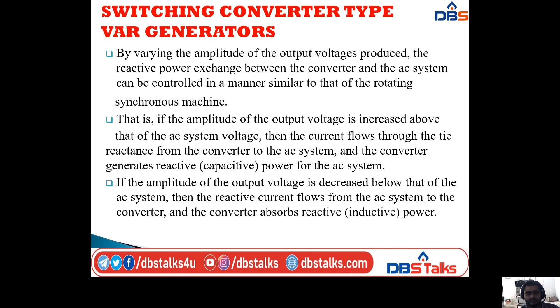If the amplitude of the output voltage is decreased below the AC system voltage, reactive current flows from the AC system to the converter, and the converter absorbs reactive power. If the output voltage amplitude equals the AC system voltage, the reactive power exchange is zero.